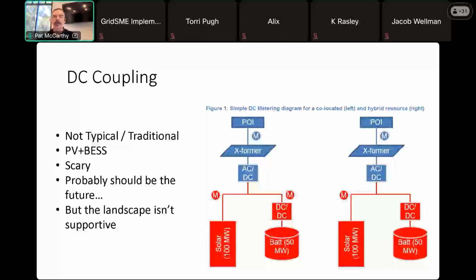The losses, if calculated live, like in a peer-to-peer consideration or implementation, are actually reduced significantly by grid charging, because in a peer-to-peer application, real losses are applied to the metering. So if you have less energy flow through transformers and transmission lines because the energy is actually flowing across your medium voltage bus, that reduction in losses will be reflected in your settlements.